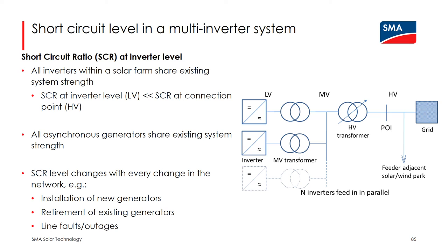And therefore, there are two main things I would like to highlight on this slide. The very first one is that the short circuit ratio at inverter level is typically well below the short circuit level which is given at the point of interconnection. So from an inverter manufacturer's perspective, we are talking about a way lower short circuit ratio than what is typically discussed when speaking to the NSPs or AEMO.